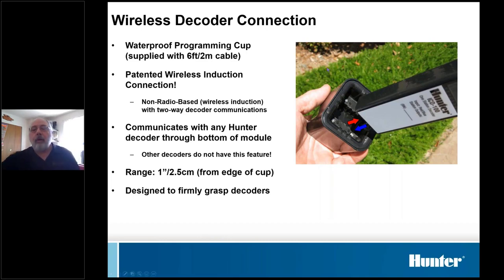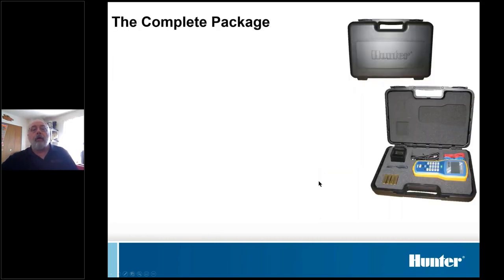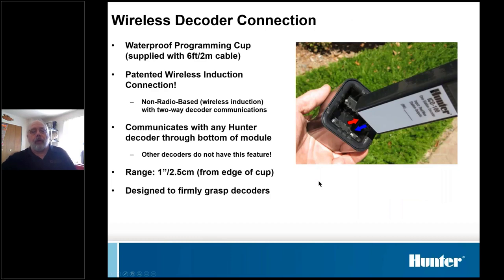So if somebody didn't install it with real tight wires and the decoder's laying down the bottom of a box and can't really get it up where you can put the programmer on, if you can put the programmer down and get within about an inch of the bottom of that decoder, it'll read it and you can program it. I'm not encouraging you to install them that way, but if you do, it'll work.